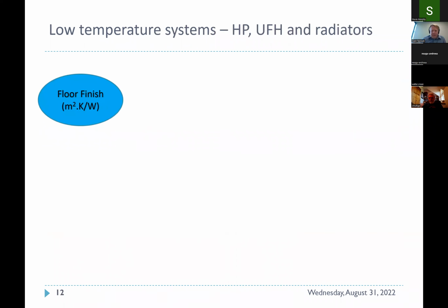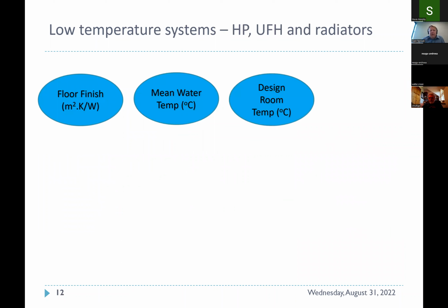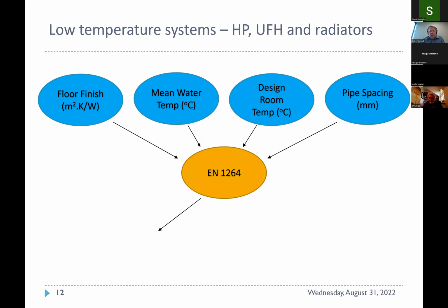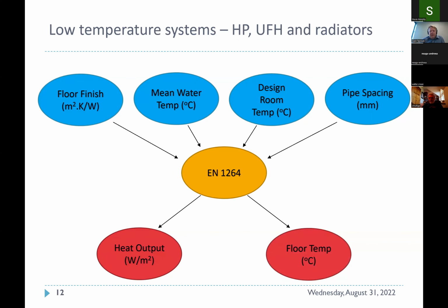A few things that are very important for floor heating systems are the floor finish, the temperature, obviously, flow and return that we send in, design temperature, and the pipe spacing. Typically, this is done at 150 mil. These are all governed by EN 1264, and based on all of the above, we will get the heat output, watts per square meter, and the floor temperature that we will achieve in the room. Typically, you will not exceed 29 degrees at floor level, to ensure that from a comfort point of view it's not too hot, and also that we're not going to start to create convection and bring dust and allergens into the air.